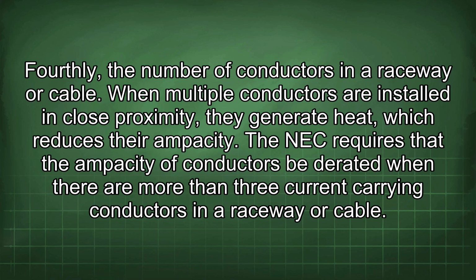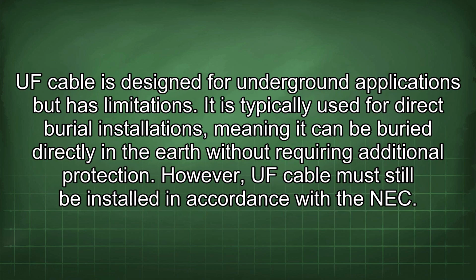Fourthly, the number of conductors in a raceway or cable. When multiple conductors are installed in close proximity, they generate heat, which reduces their ampacity. The NEC requires that the ampacity of conductors be derated when there are more than 3 current-carrying conductors in a raceway or cable. UF cable is designed for underground applications but has limitations. It is typically used for direct burial installations, meaning it can be buried directly in the earth without requiring additional protection.